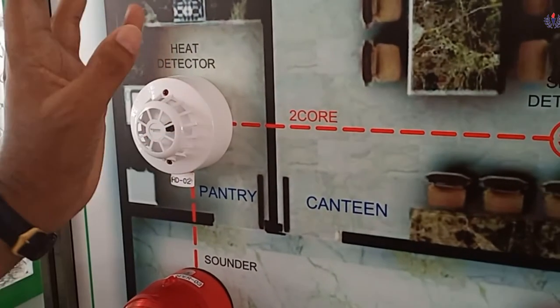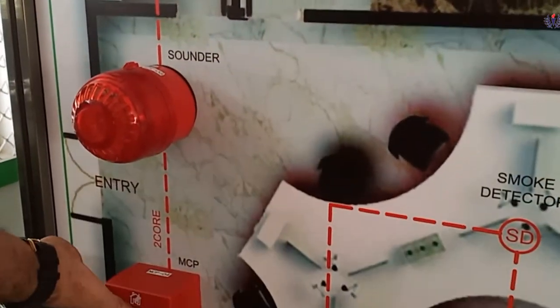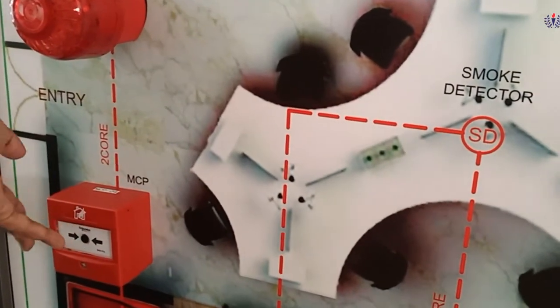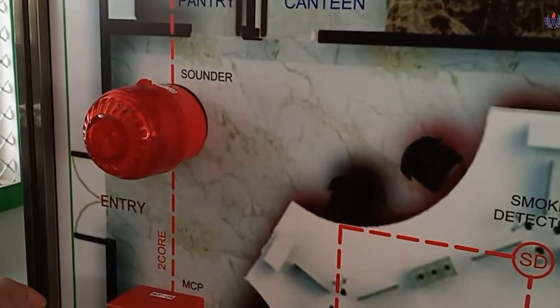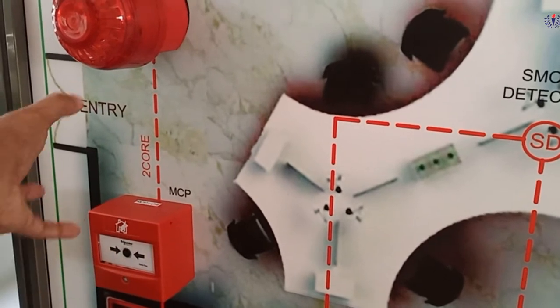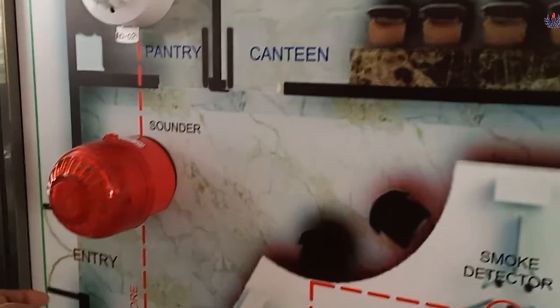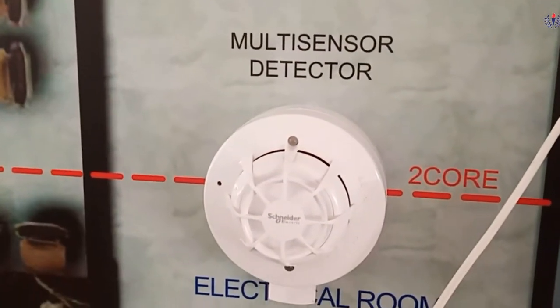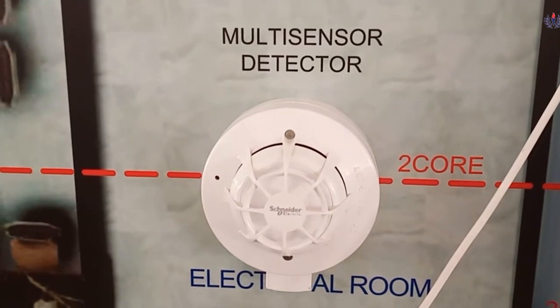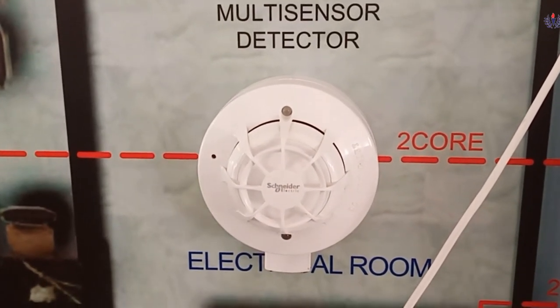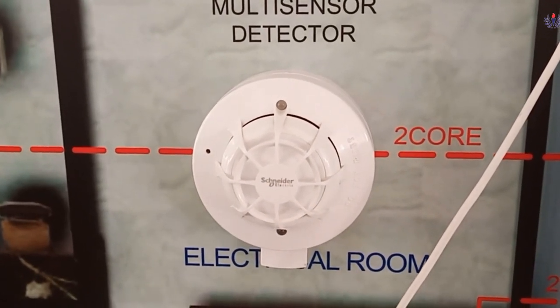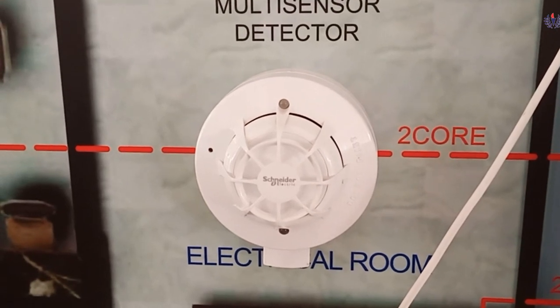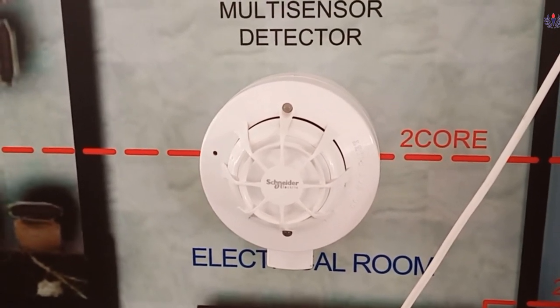In the first application, I have to press this manual call point. I have to check whether the hooter is working and the sounder is working. So in the first application I'm going to press this so that the fault will be created manually. Now the device is almost ready. Just now we have seen the blinking. Once again it takes about 2 seconds to start.